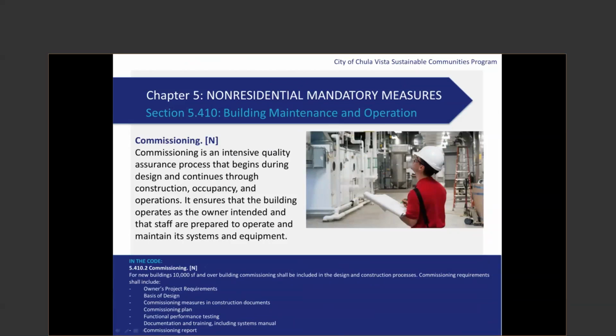documentation and training, including a systems manual, to ensure the operations team knows how the systems are meant to work. The operations team is the key factor in ensuring a building is maintained and continues to operate as it was designed. And finally, a commissioning report is required. In the Energy Code, no matter the size of the project, you must go through a commissioning design review to ensure the owner's project requirements and basis of design are reflected in the design shown on the construction documents. So my key takeaway here is get your commissioning agent on board before the design phase, during the design phase.